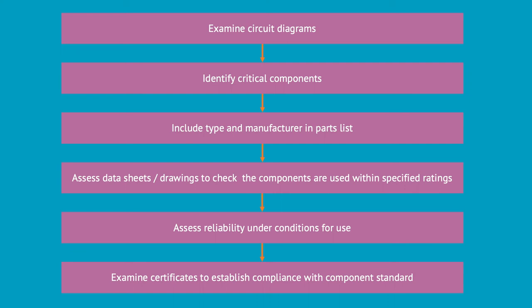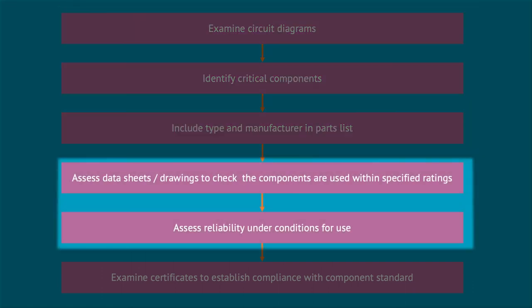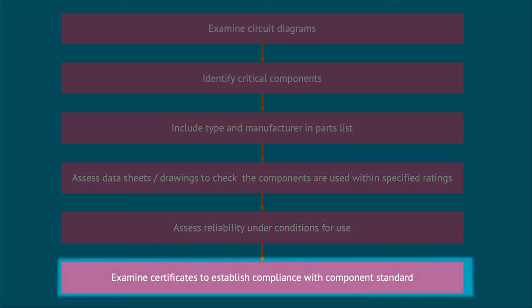To explain the approach the test house will apply, it will probably look something like this. The critical components are identified by examination of the circuit diagrams. Then their type and manufacturer are identified in the parts list or bill of materials. Then they assess data sheets and drawings to check that each component is used within specified ratings and the reliability of the conditions for use of the device. And last but not least, they check the certificate and any limitations for the specific type of component. So it can be a very good idea to check these things yourself before design freeze.